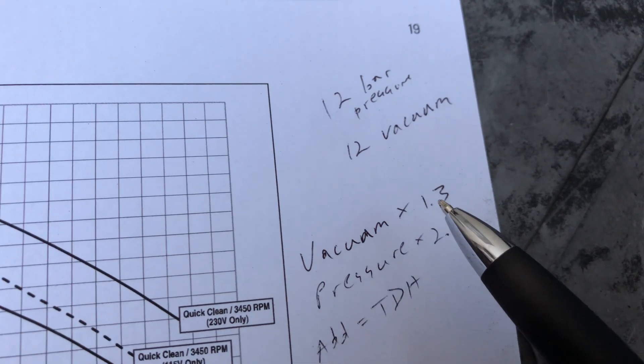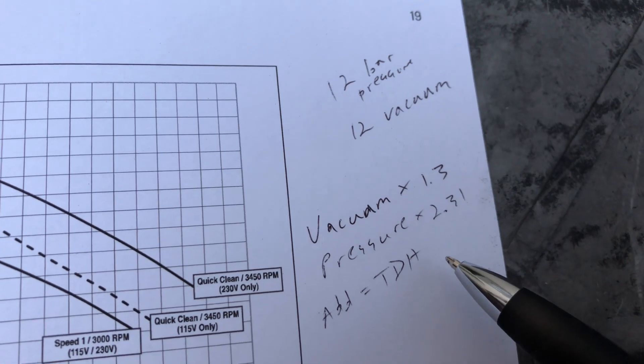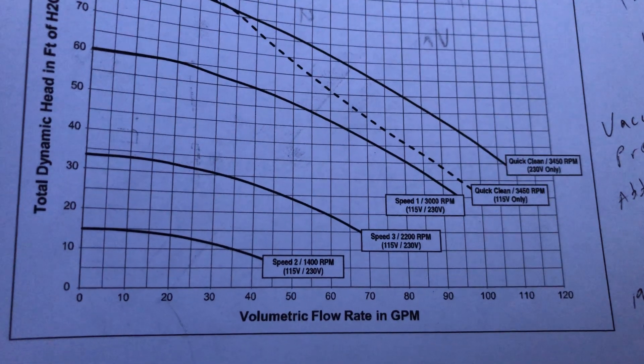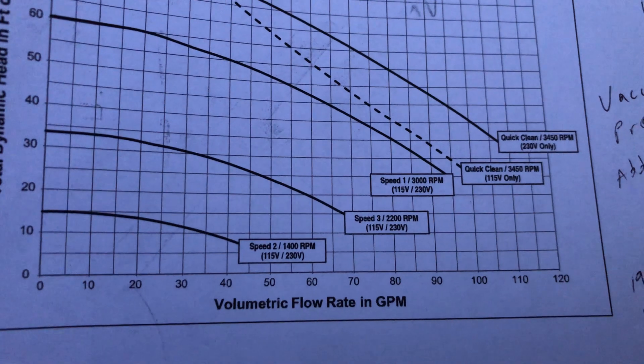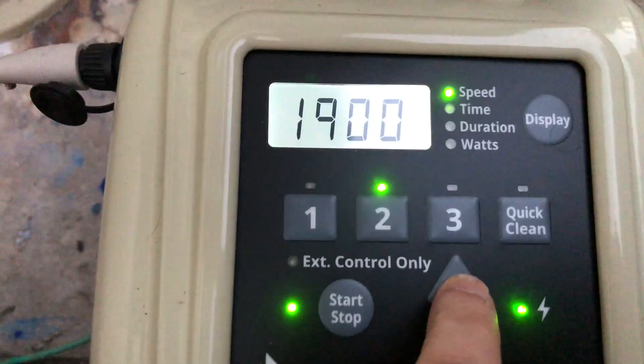So now we're going to take the vacuum number and the pressure number, and we're going to multiply those accordingly, and then add them together, which will get us our total dynamic head. And we got the reading at 3,000, so let's grab what the curve is at 2,200 RPM as well. So let's crank this up a little bit.